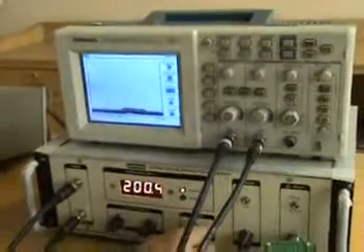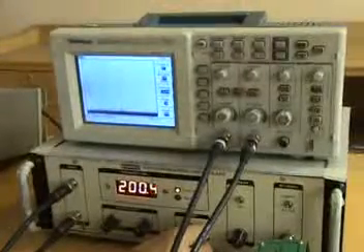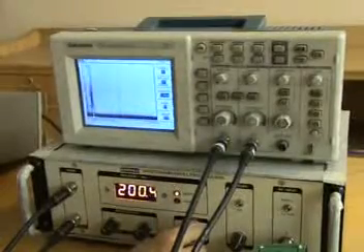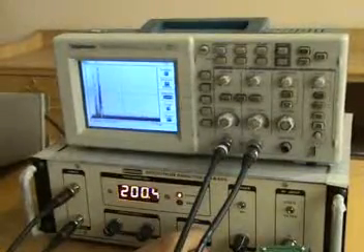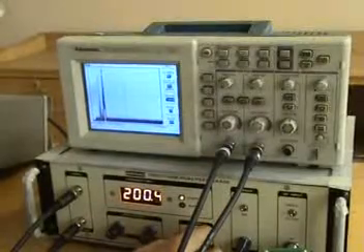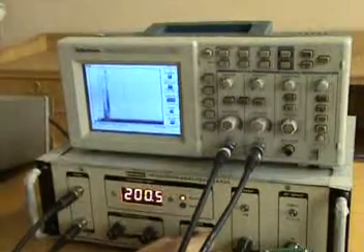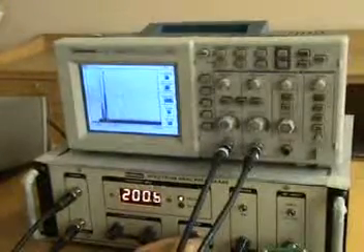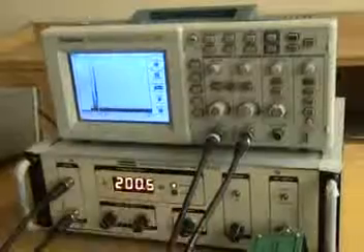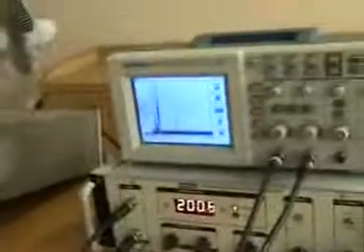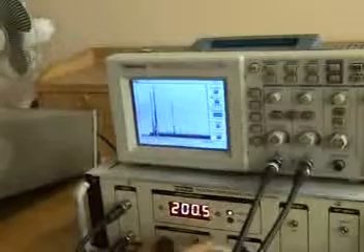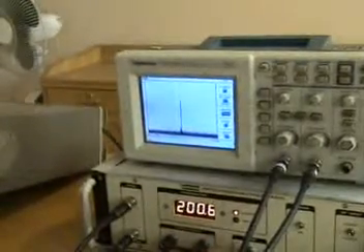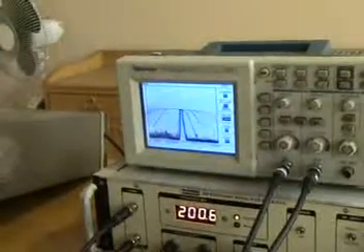So once again, by increasing the sweep width, mind it that when the pot is going clockwise, the sweep width is increasing. It is now in hundreds of megahertz, whereas if we decrease, it goes in a few kilohertz. So right now it is maximum, and if we want to see any signal, that signal once again has to be brought to the center of the display, and then the sweep width has to be decreased.